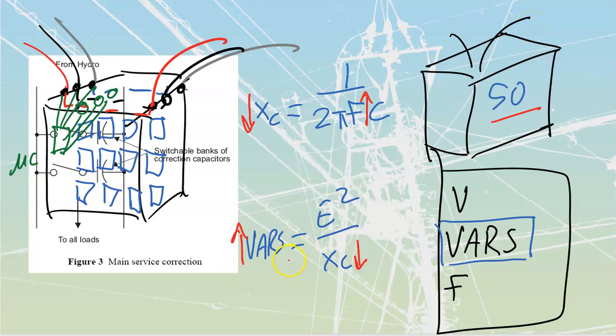And how much it's actually going to increase the current feeding to the bank, etc., because our VARs have gone up, therefore the amount of capacitive current has also gone up. Voltage has stayed the same, but voltage changes also make a difference. If I connect something to a larger value of voltage than it's supposed to handle, I'm obviously going to blow that thing up. Now, we're not going to look at that, because only an idiot would take something rated for 208 volts and put it onto a 600 volt system.